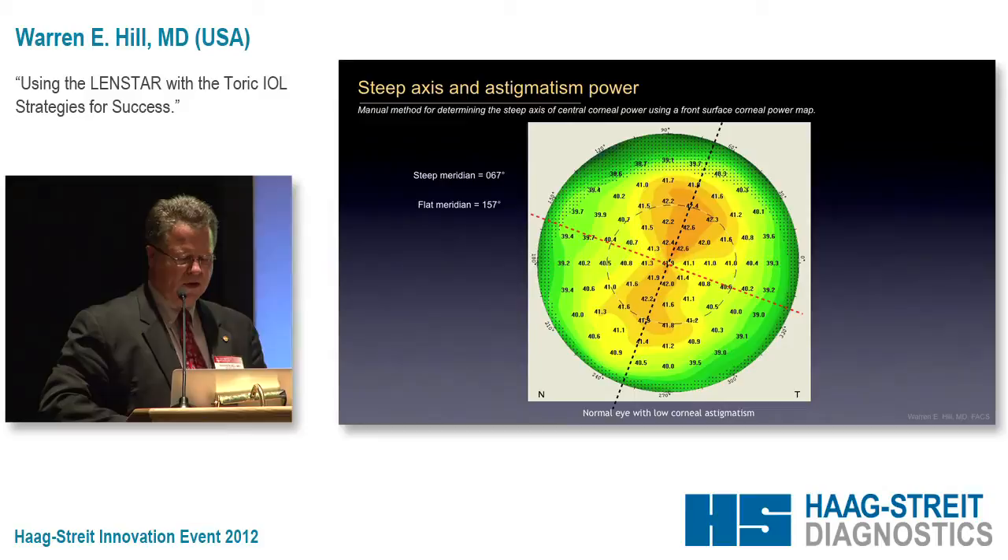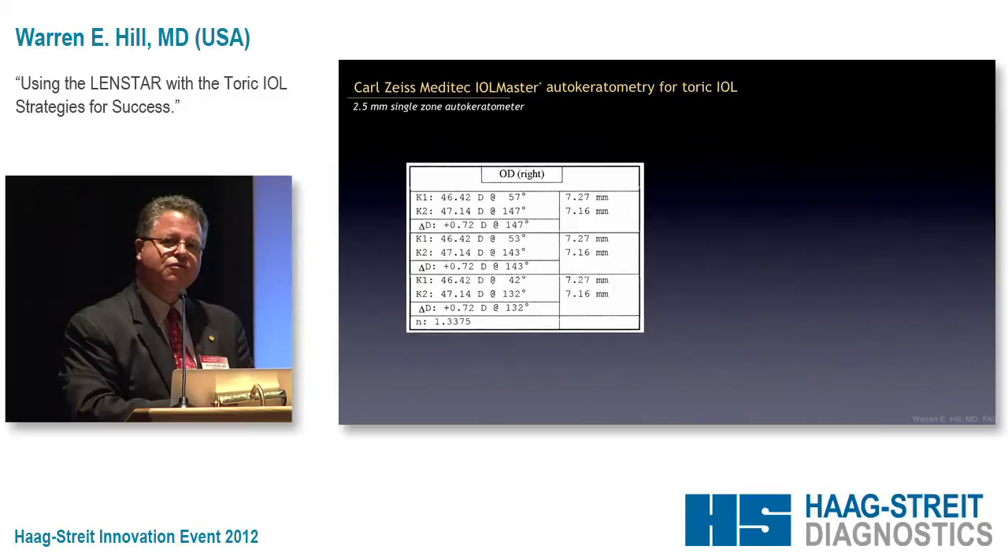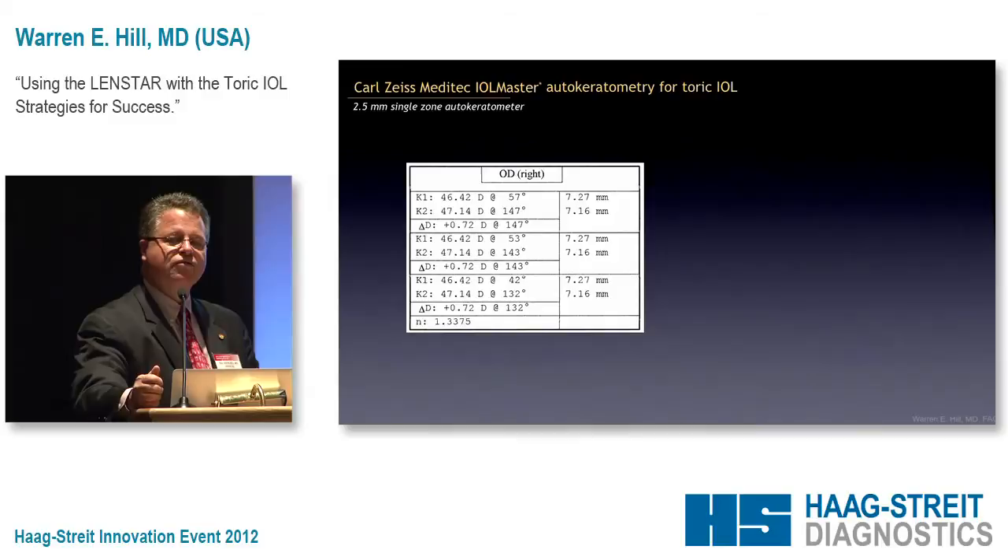How many of you use the IOLMaster? Pretty much everybody's hand should go up, because that's what you're using — you probably haven't got the LENSTAR yet, that's why you're here. Zeiss never intended the IOLMaster to be used for the toric IOL, although that's what most people use because it's easy to do. It was intended to determine the spherical power of the IOL — K1 plus K2 divided by 2. One of the paradoxes of the IOLMaster is for a lot of patients it's dead on and works wonderfully, but then for a subset of patients it's awful and we have absolutely no idea why.